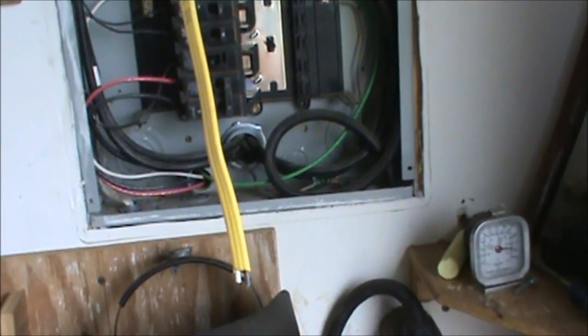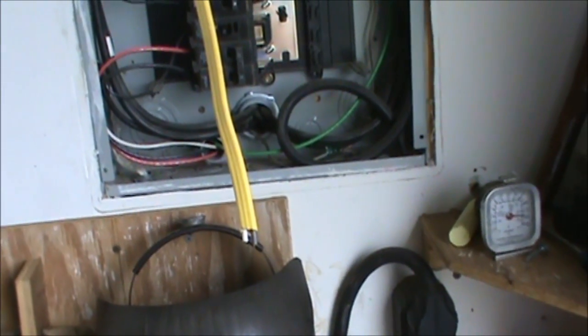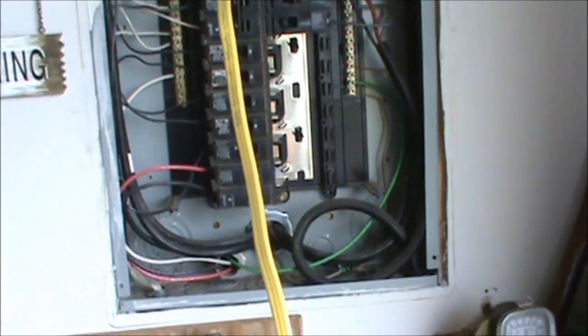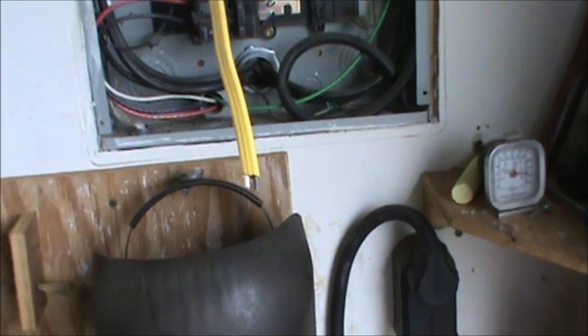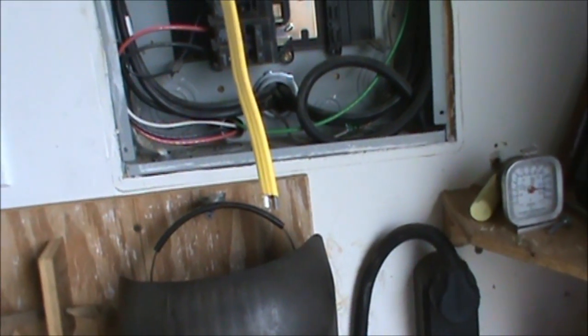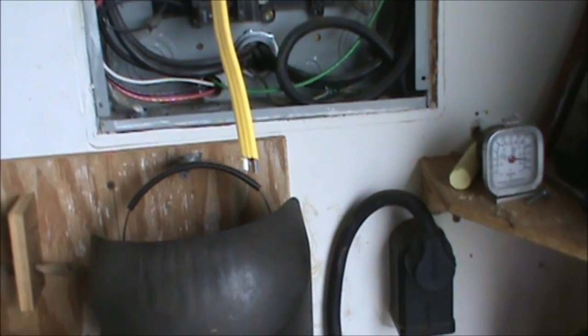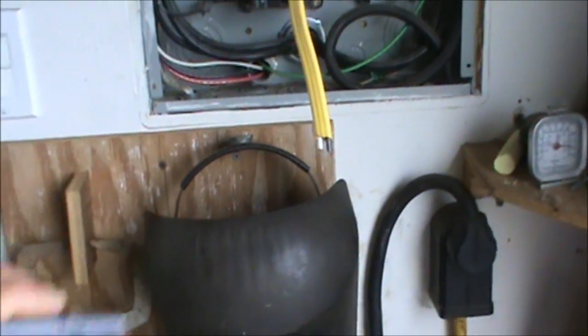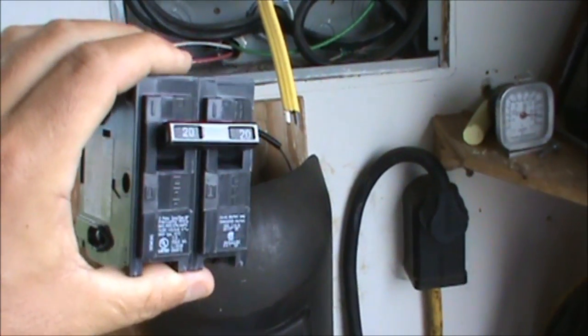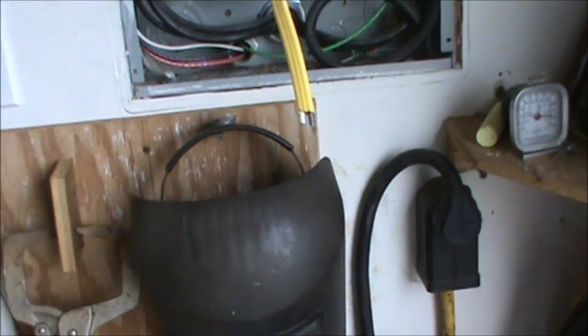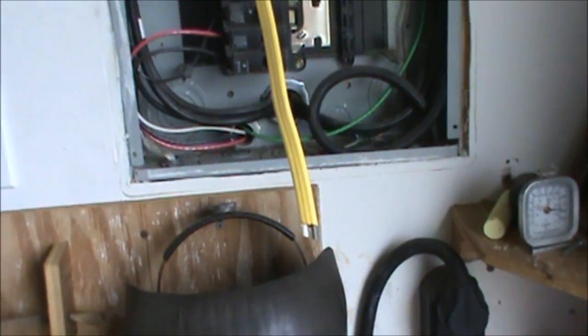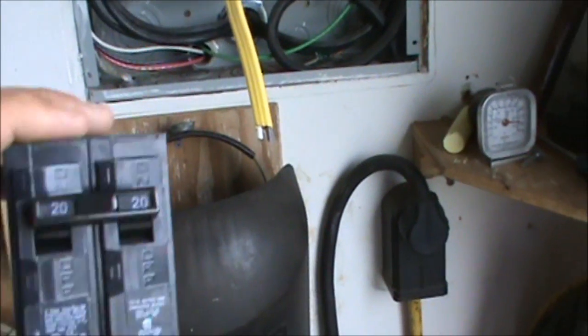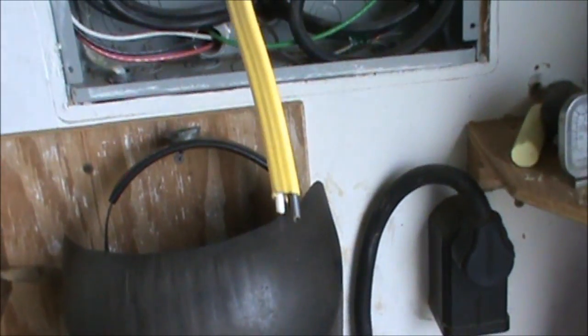You're also going to need to run 12 gauge wire. 12 gauge wire is a little bit thicker than your standard 14 gauge that you use for most house wiring. In basic terms, whenever you use 12 gauge wire, you need to use a 20 amp breaker. We're going to wire it up for 240, so we need a double. Basically, if you have 14 gauge wire, you're going to need to use a 15 amp breaker, but we're using a 20 amp breaker so we need 12 gauge wire.